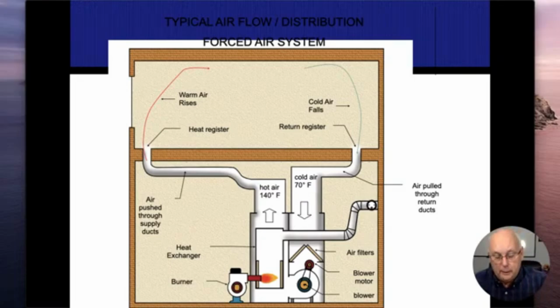Now, if I had the fan running down here, that fan on this side of the fan, the filter side, is going to be under a negative pressure. After the fan, it's going to be under a positive pressure. If I ran this pipe through the negative pressure and I had a hole or a crack or something where we saw that rust corroding it, I'm actually going to be creating a vacuum and pulling the bad gases and the carbon monoxide into my circulation air. So we don't want to have any sort of venting running through a low pressure zone like any ductwork that's going to be before my blower fan.